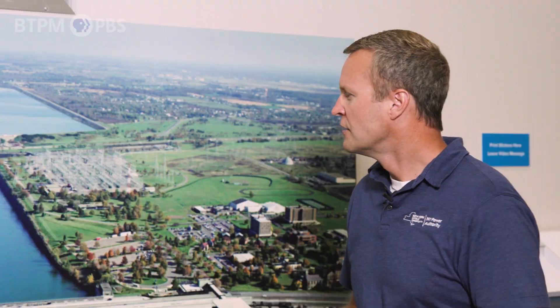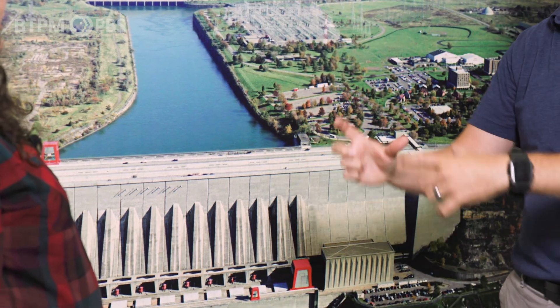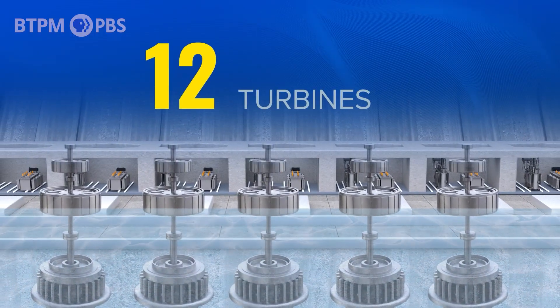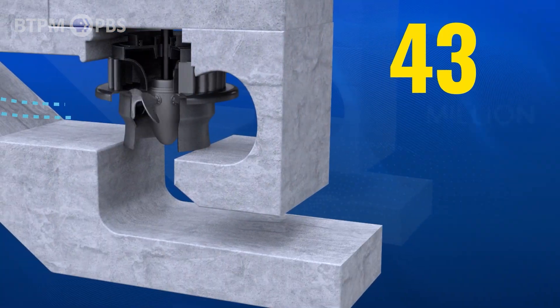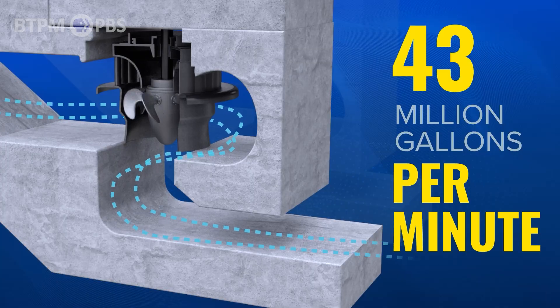On days where it's really hot and everyone's using their air conditioning, you can change it accordingly. So how do we use the water to create electricity at this plant? As water comes down our forebay, it travels into our penstock — just a big tube that brings water down into the turbine. Water then flows through the turbine, which causes it to spin, kind of like a big old water wheel. At that point, you're converting your water energy, or the flow of falling water, into mechanical energy.